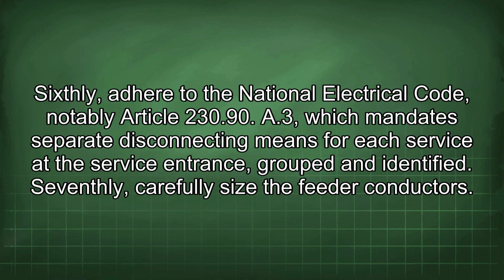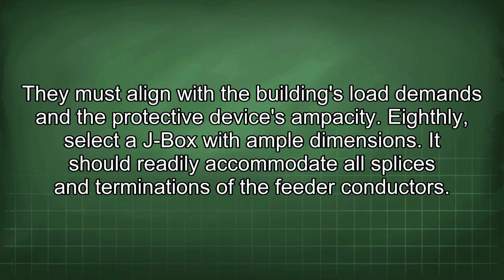Sixthly, adhere to the National Electrical Code, notably Article 230.90(A)(3), which mandates separate disconnecting means for each service at the service entrance, grouped and identified. Seventhly, carefully size the feeder conductors. They must align with the building's load demands and the protective device's ampacity. Eighthly, select a J-box with ample dimensions. It should readily accommodate all splices and terminations of the feeder conductors.